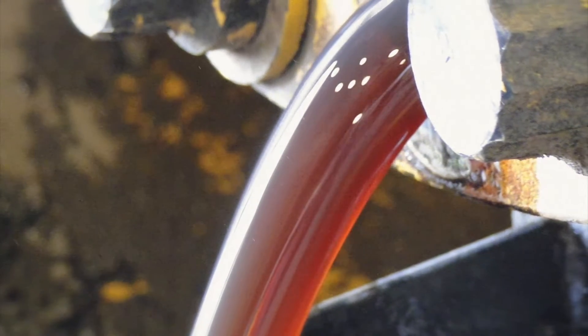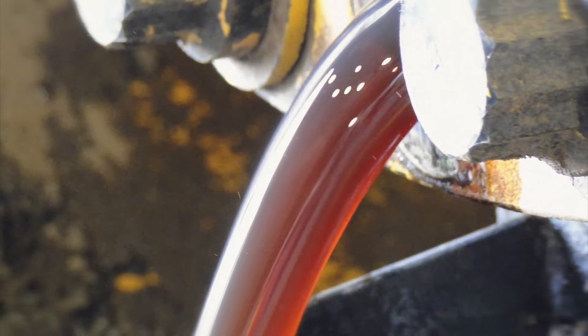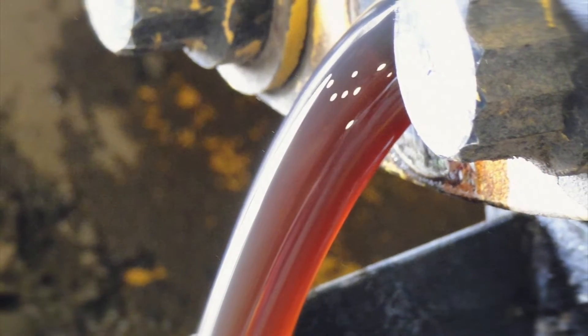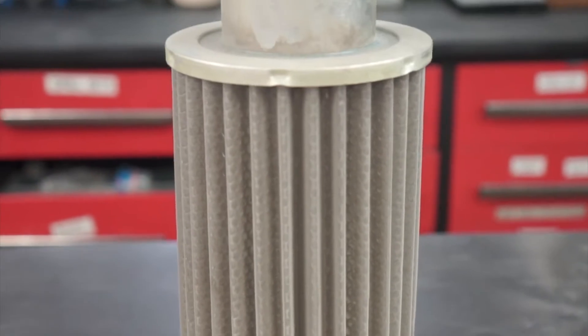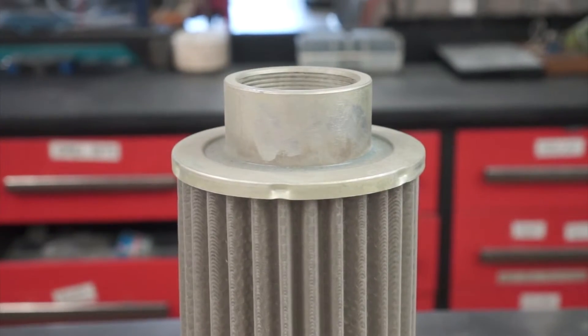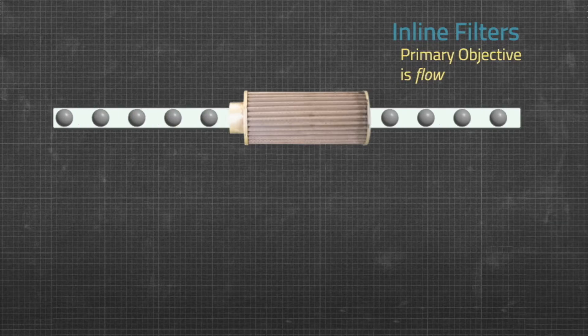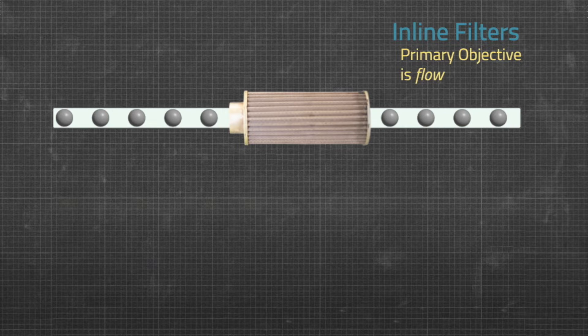It's inevitable that particles, water, or oil degradation products contaminate the oil. And an inline filter can do an adequate job of trapping some of the larger particles. However, millions of very fine particles and soft contaminants fly right through the filter at breakneck speed and continue circulating in the system, leading to operational issues or long-term damage to bearings and other components. The inline filter is so concerned with passing enough oil to satisfy the needs of the system, it fails to live up to its moniker as a filter.